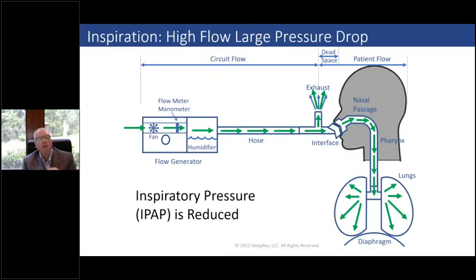Why is that important? Well, when you're breathing in, you have high flow in the circuit because you've always got the exhaust flow blowing on the bed partner. That's always got to be there. The only way it drops is if the pressure drops, because it's based on a gradient across the little hose. So you've got that flow.